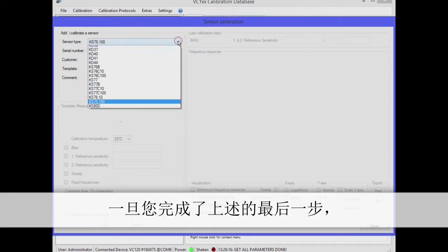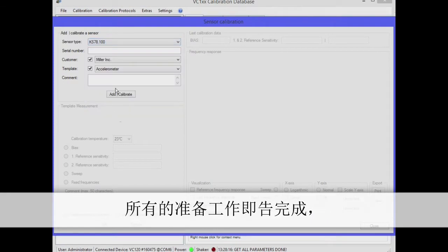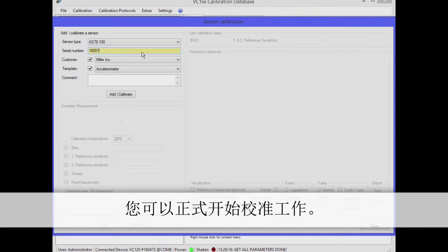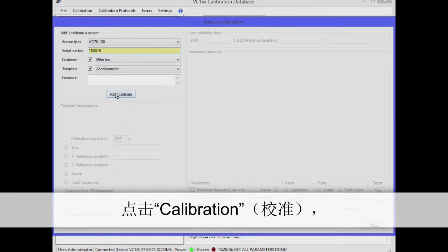Once you have completed this last step, all preparations are finished and you can start with the calibration. Click on calibration. Then select a sensor type, enter the serial number, select the customer and then the template.